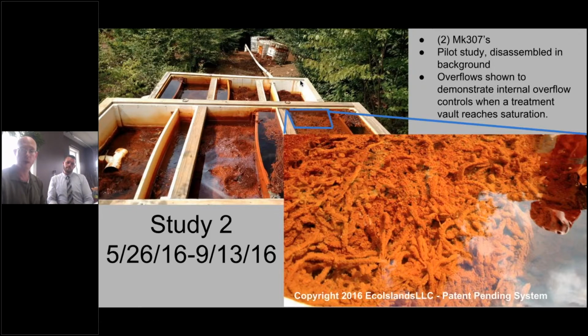And you can see it actually here in the background. And we decided to go on to 2 true MRUs. One's using weirs and vaults and a much higher rate of flow through. Now the overall flow on this system, total flow, was somewhere around 100 gallons a minute. So when we're taking off 4 gallons a minute, it's a drop in a bucket.